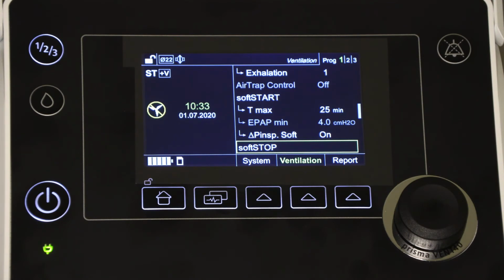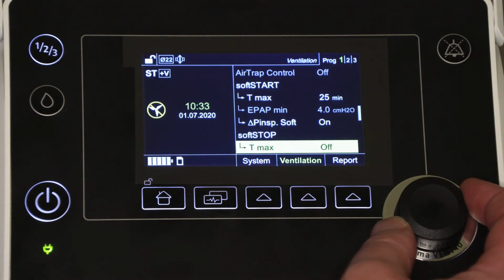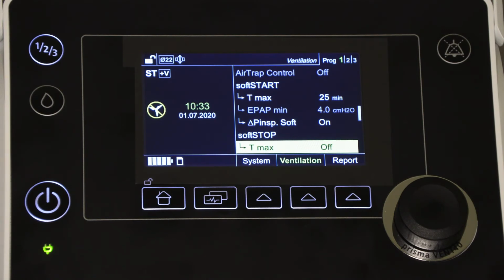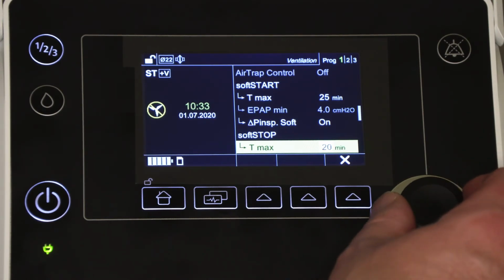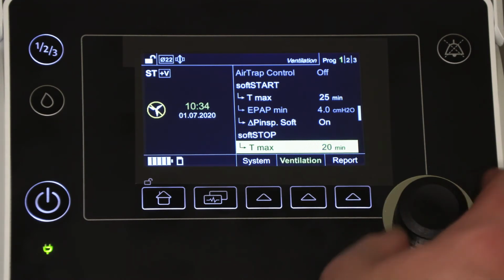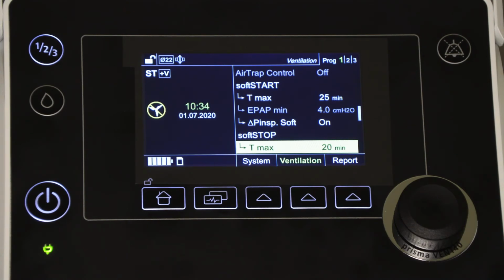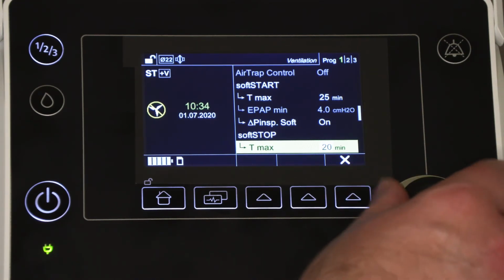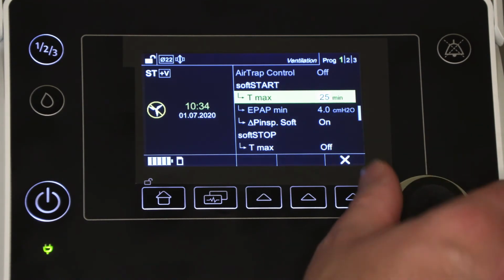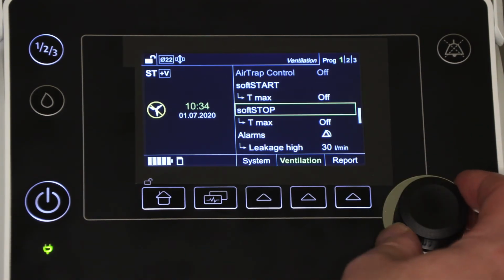Soft stop is an additional feature which will apply a gradual descent of therapy pressures when the user decides to turn the ventilator off. This can be useful for patients who don't like the feeling of the sudden disappearance of therapy pressure when the ventilator is turned off. By setting a soft stop Tmax time, it means at the end of therapy, when the user tries to turn off the device, instead of just shutting down immediately, it will gradually wind down the therapy pressures over the time period set as the soft stop max, and will then shut down at the end. The soft start and soft stop can be left turned off if not required.